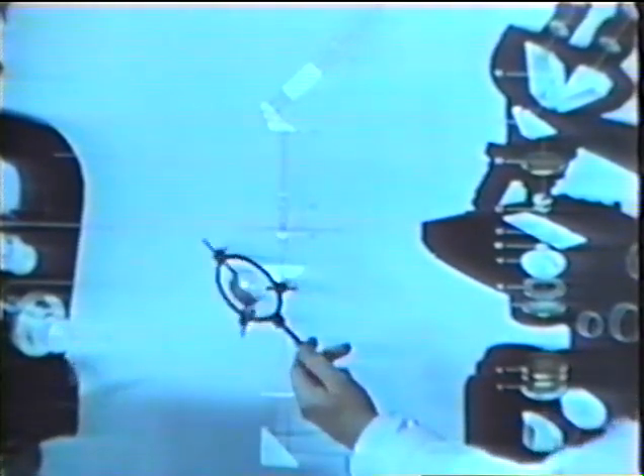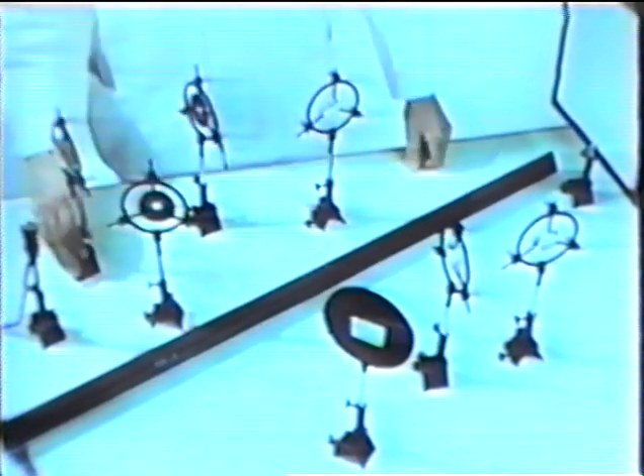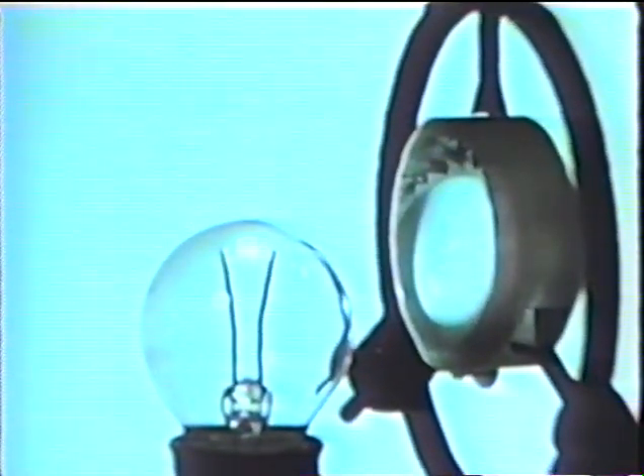We shall now build a model microscope, replacing complete lens combinations by separate single lenses. The whole is built up on an optical bench, and from all these separate parts we begin, in correct order, with the lamp and its incandescent filament. After the lamp, a lens is inserted — the lamp collector. Then immediately an iris diaphragm with variable aperture, known as the radiant field stop.